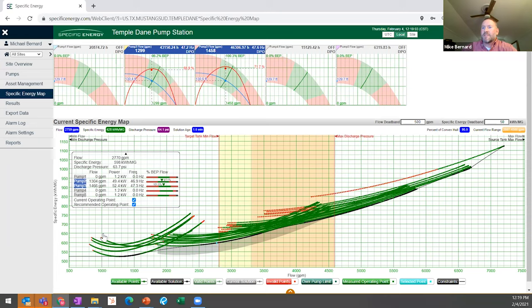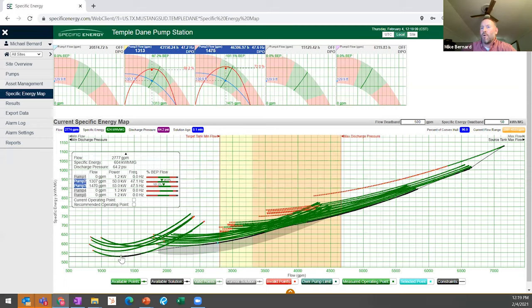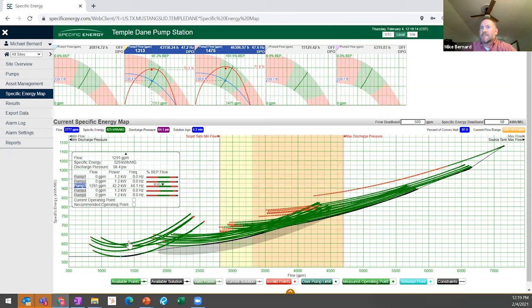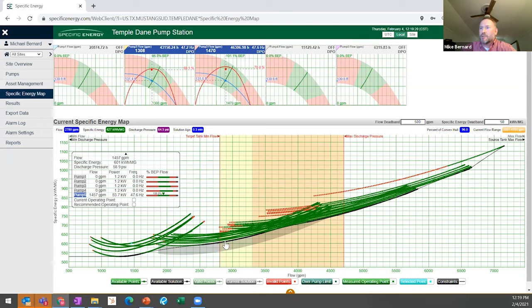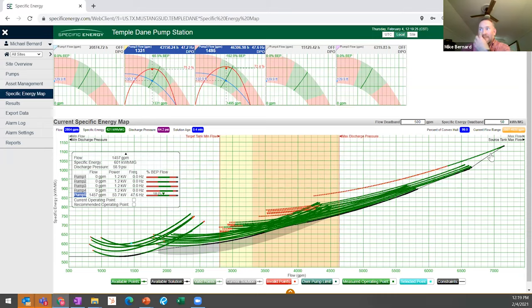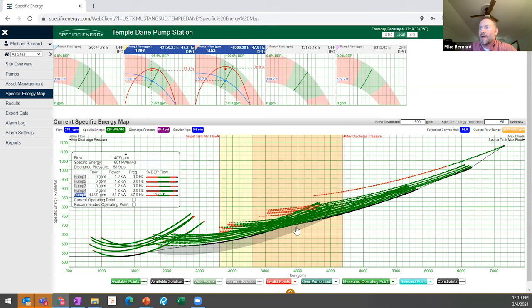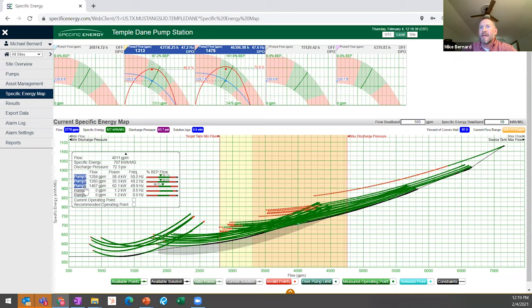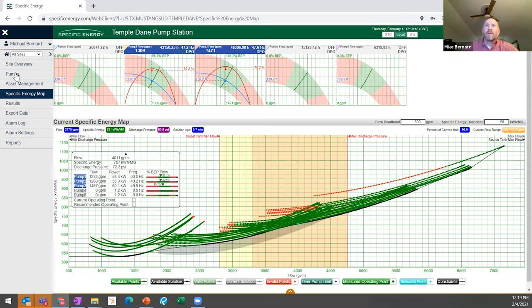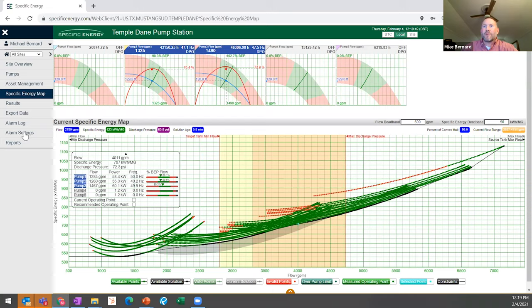There's a number of other constraints that can be configured: minimum and maximum suction pressure, minimum maximum flows. There's even a power limit that you can put on in here if you're under a curtailment program or something like that. Once all of the constraints are enabled, the DPO automatically draws this box. We call this the sandbox because this is where the DPO is allowed to play. The DPO's job is to find the point that is at the minimum spot of specific energy with all of the pumps within their preferred operating range that meets this. You can see that little green dot moving around there very close to this point right here, which is what it's supposed to be doing.